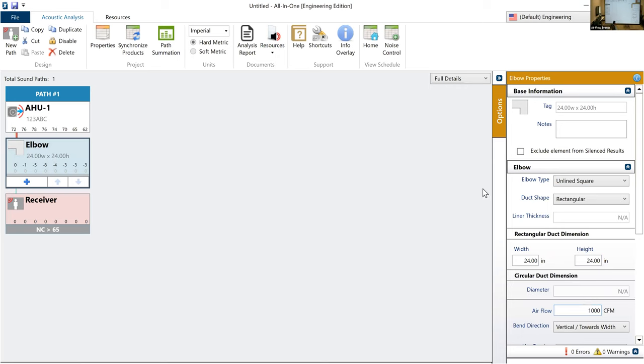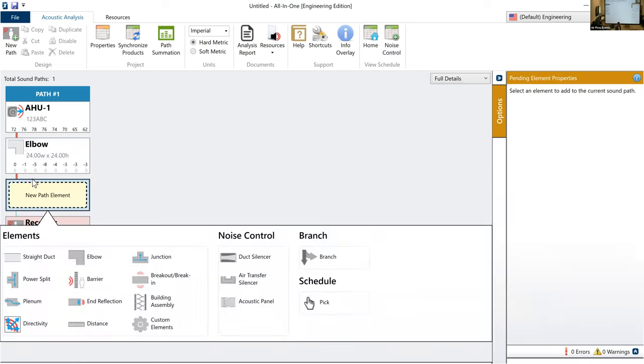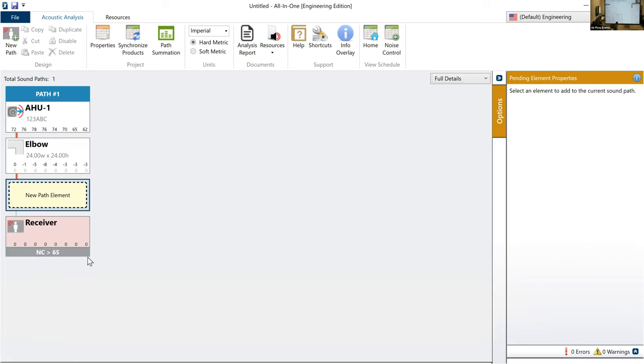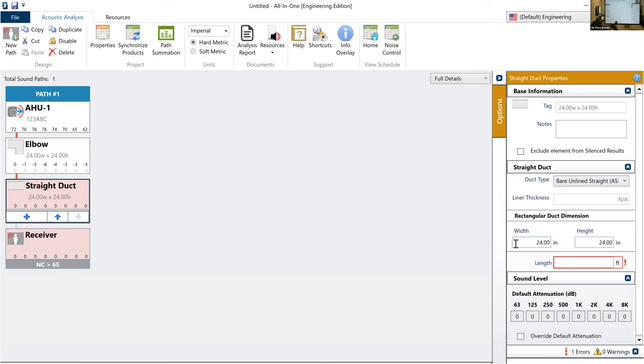One of the really nice things with the software is it pulls information forward from the previous element. I put in 1,000 CFM, that elbow element knows that it was 1,000 CFM, and it's going to continue through in that nature. The next element I'll pick is a straight duct. Again, all those dimensions are going to get pulled from the elbow, 24 by 24, and I'll put in 20 feet of straight duct.